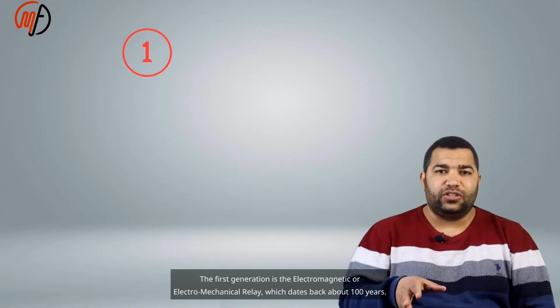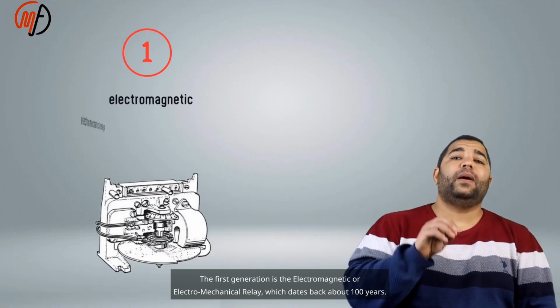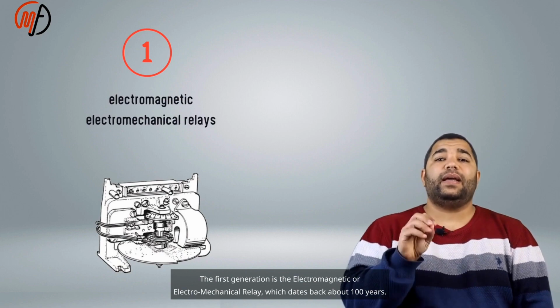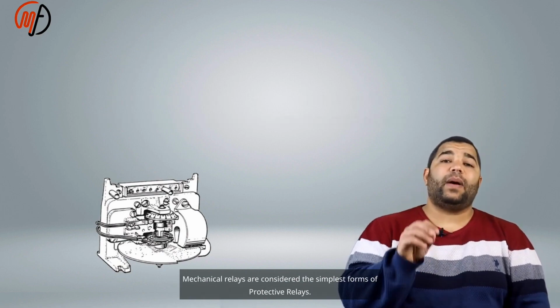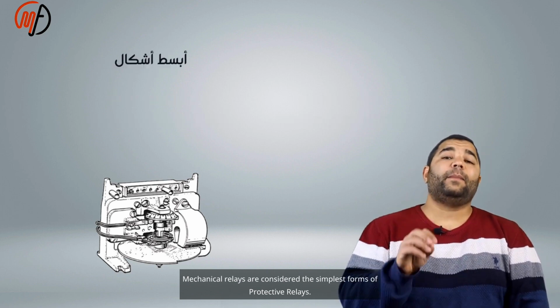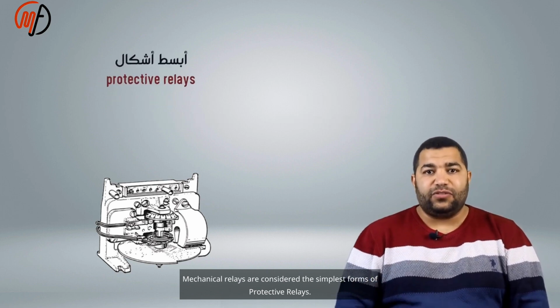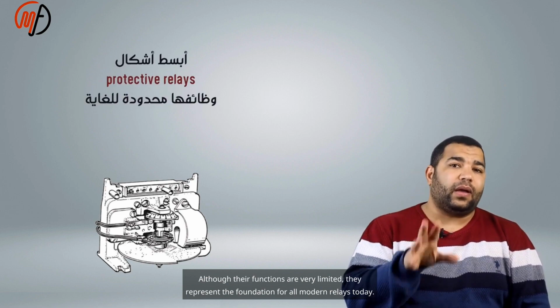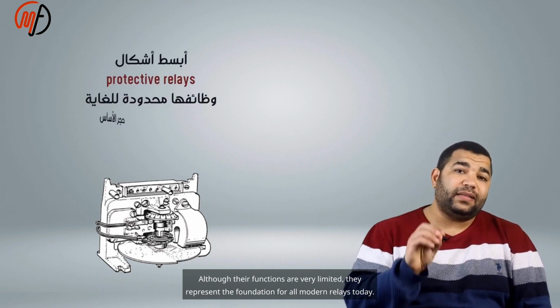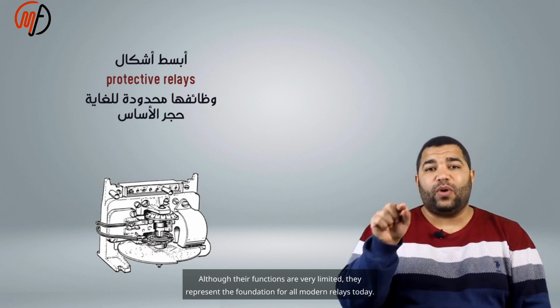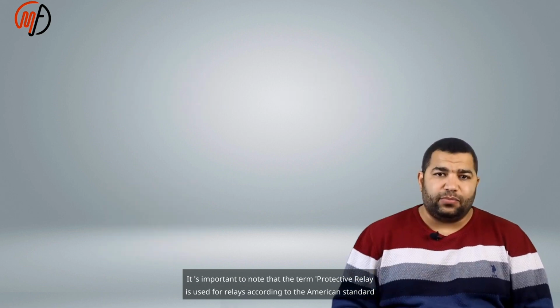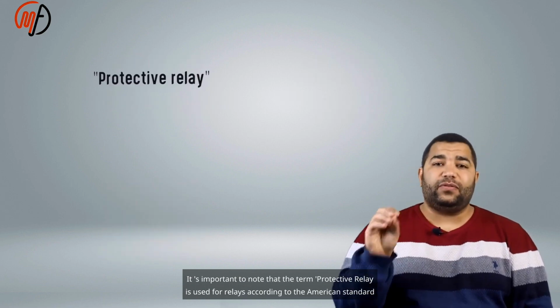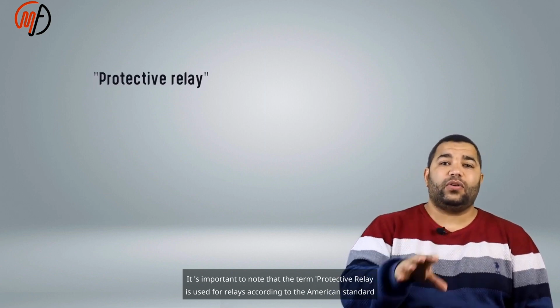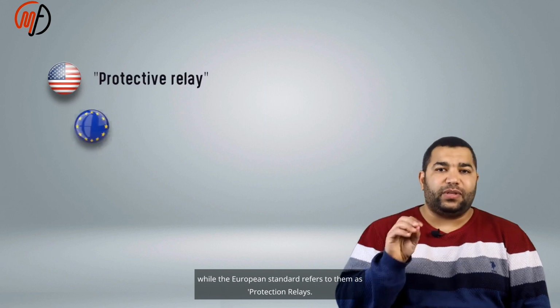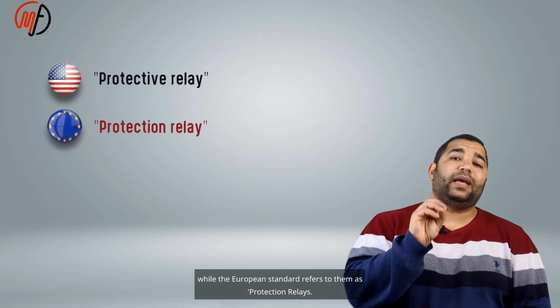The first generation is the electromagnetic or electromechanical relay, which dates back about 100 years. Mechanical relays are considered the simplest forms of protective relays. Although their functions are very limited, they represent the foundation for all modern relays today. It's important to note that the term protective relay is used according to the American standard, while the European standard refers to them as protection relays.